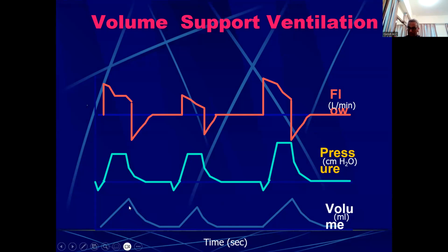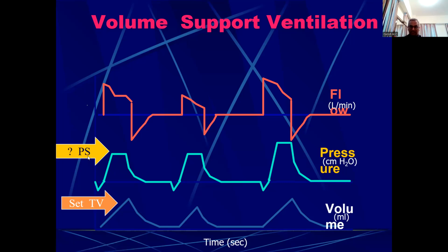So what does the machine do? The machine tries to give 2-3 test breaths and it determines how much pressure is needed to achieve that tidal volume. It will give you 5 centimeters, 8 centimeters, 10 centimeters and sees how much tidal volume is generated. And if whatever you have set is reached, it will keep giving that tidal volume. Now, in this mode, you set the tidal volume, the machine determines the pressure support by giving test breaths, and it determines, okay, this much pressure is needed to achieve this tidal volume.